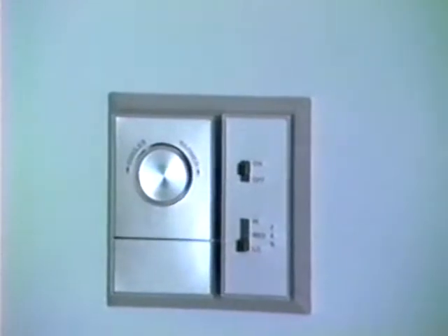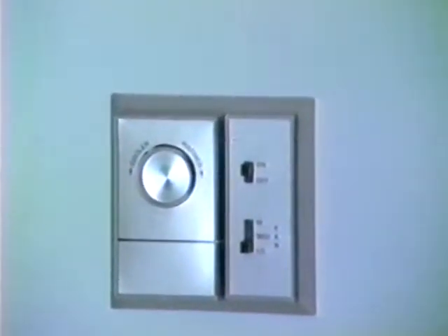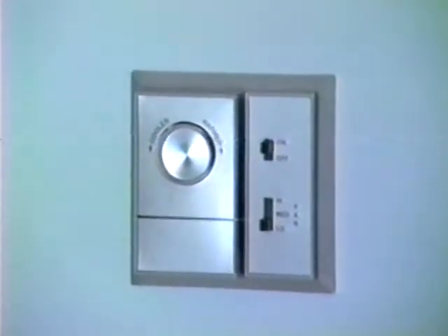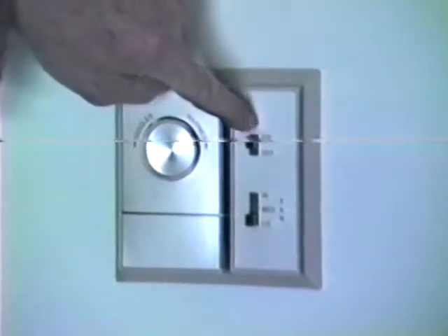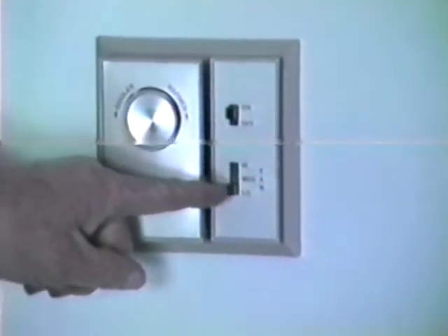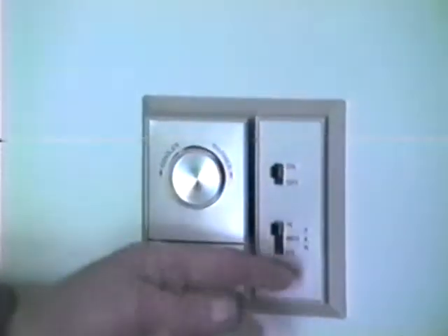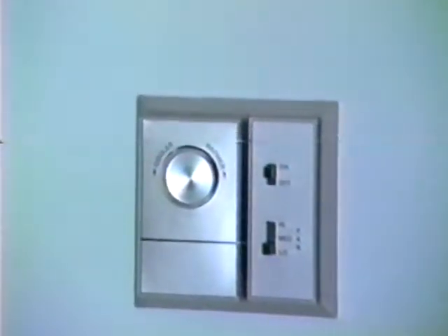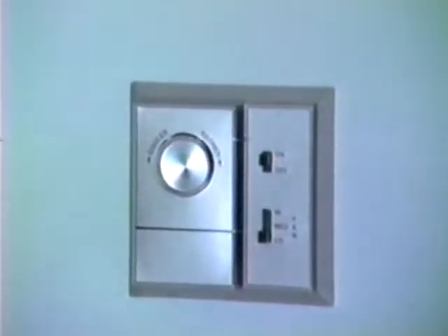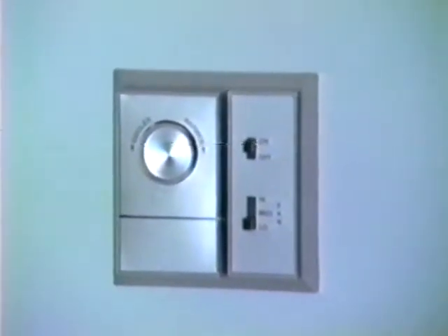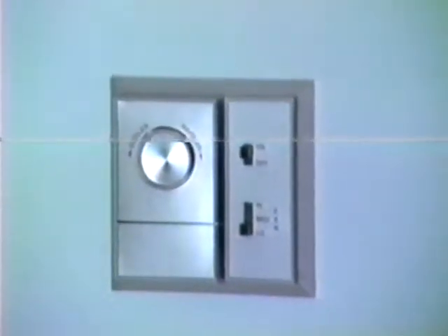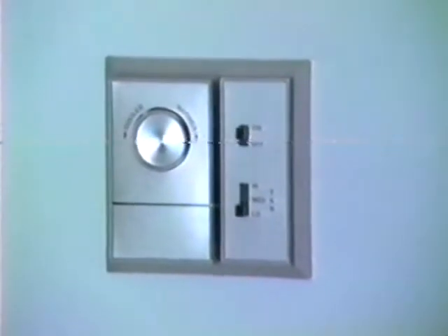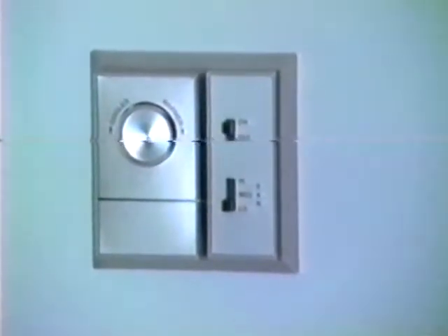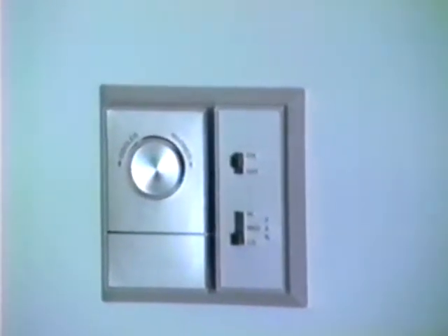This is our typical room thermostat. The dial on the left has a warmer or cooler selection point. The switches on the right: the system switch is on or off, and below it is a three-speed fan switch. Since the thermostat has no subbase, the Aquastat that we pointed out in the fan coil a while ago senses the water temperature, either hot or cold, and tells the thermostat when to react on a temperature fall or a temperature rise. In other words, the Aquastat acts as a subbase to let the thermostat know when it's in the cooling season or in the heating season.